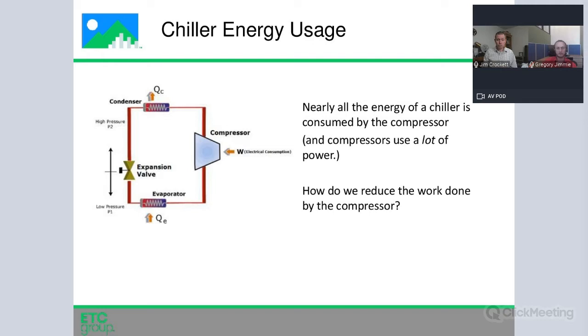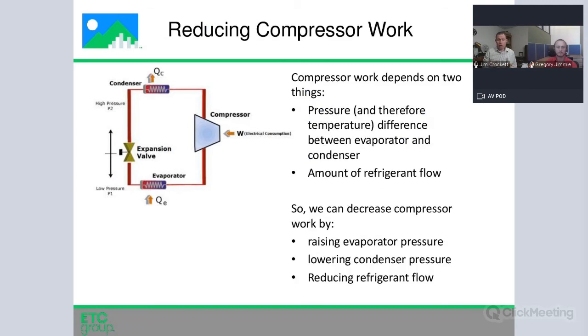And 10%, I think Greg's going to show us an example of one that was even higher than that, but 10% is a realistic number. So how do we reduce the amount of work done by that compressor? Well, again, the work that the compressor is doing is taking refrigerant at a low pressure and raising it to a high pressure. So from a very high level, there's really only a couple of ways to reduce compressor work. One of them is to reduce the amount by which we're increasing the pressure. And the second way is to decrease the amount of refrigerant being pressurized.